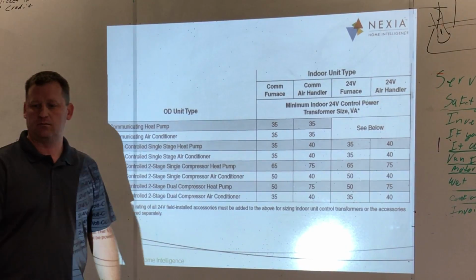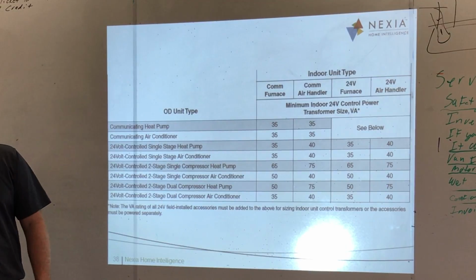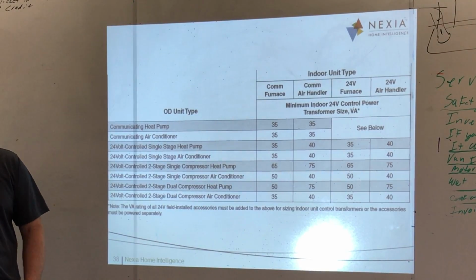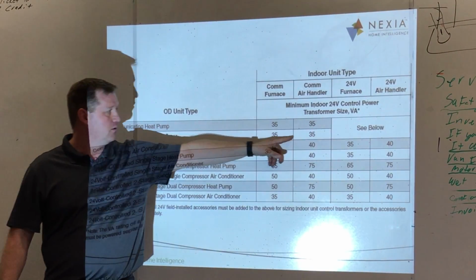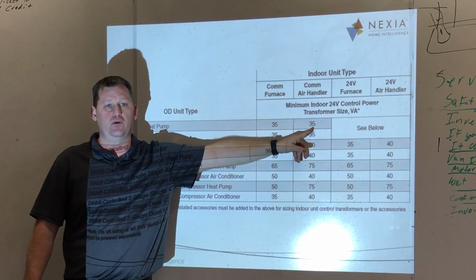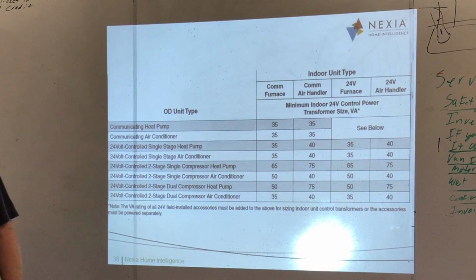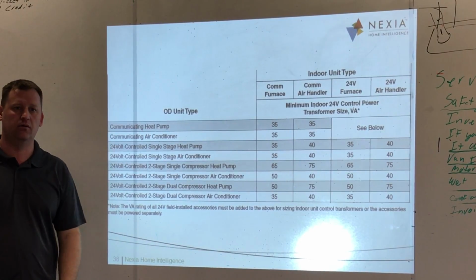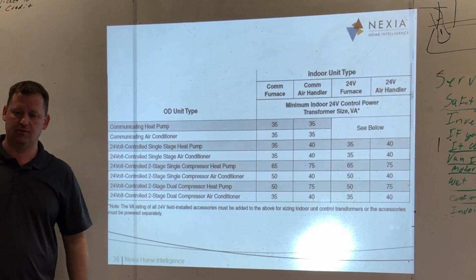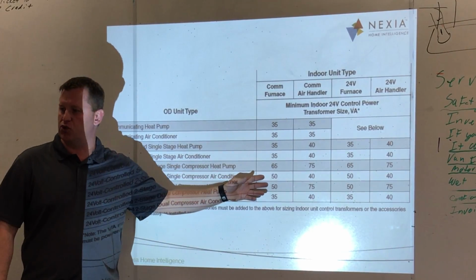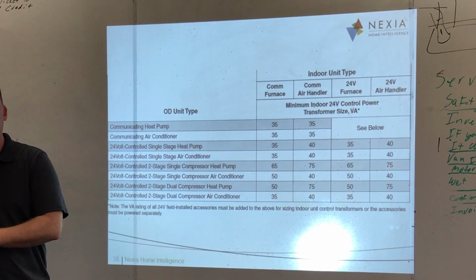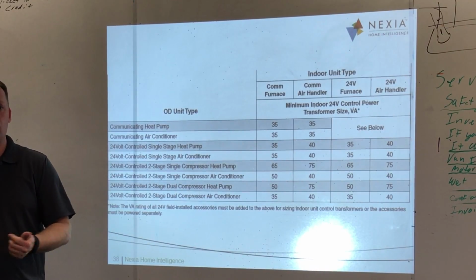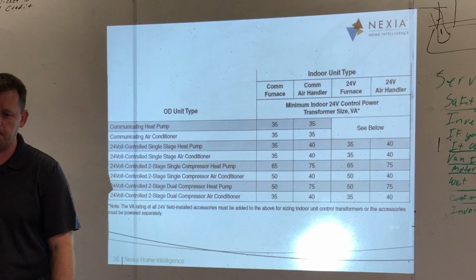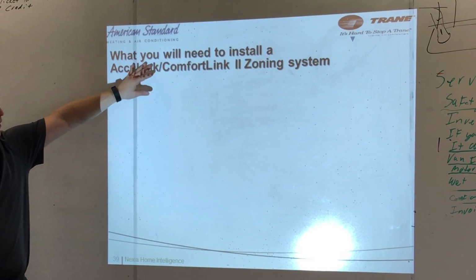What's the communicating air handler come with? What size of VA transformer? I believe it's just 50 anymore. I'd have to double check that, but I believe it's 50 because communicating, most of the time we're doing a communicating unit, 35 is enough. Plus a 17, so we're still good. Okay. You're pushing it on that. Pushing. Yeah. We like that edge. Yeah, we love the edge. And what happens, guys, is we end up with situations where when it goes into defrost, it doesn't switch over to cooling for defrost, or the whole stat will just go blank when it goes into defrost because the voltage drops too much.